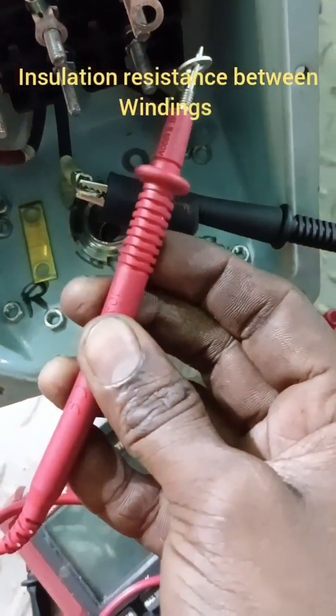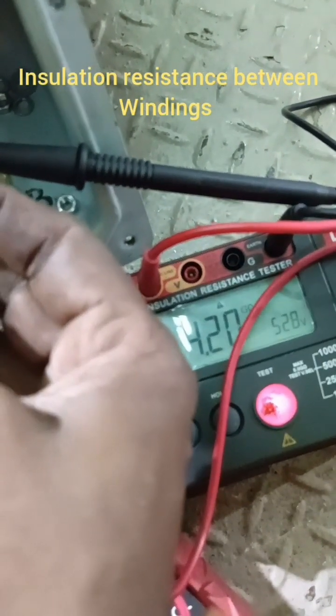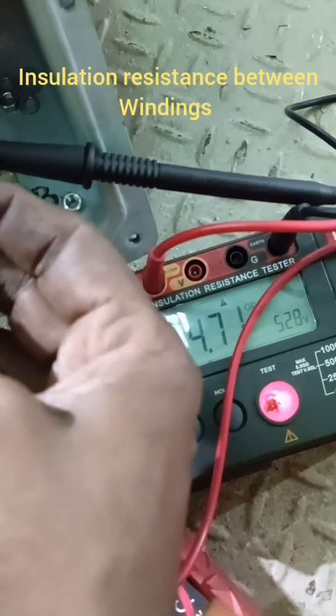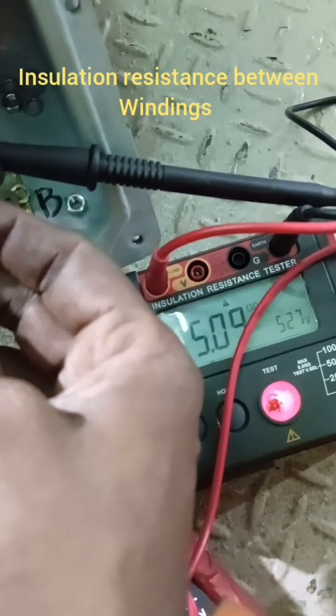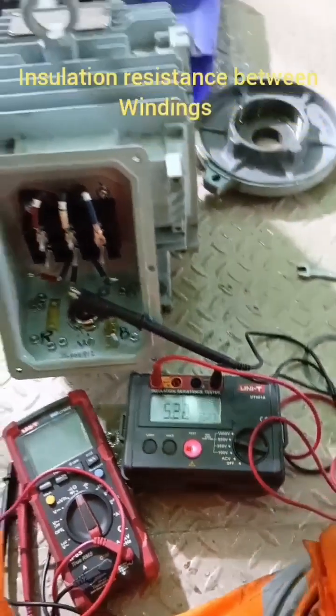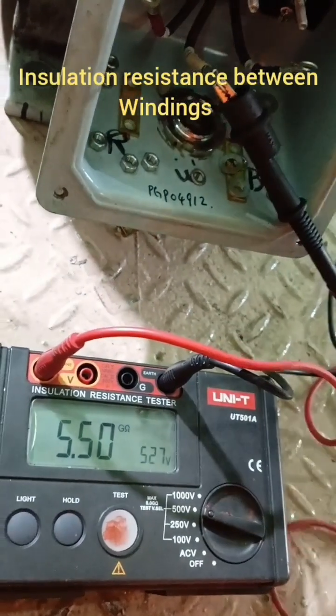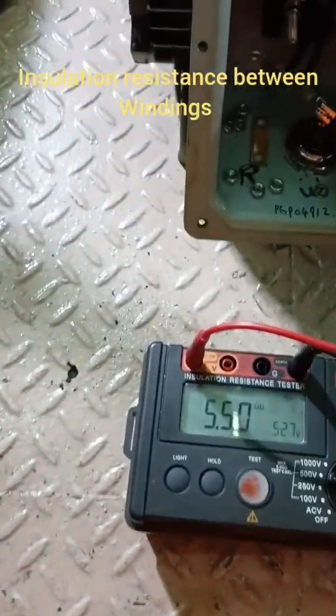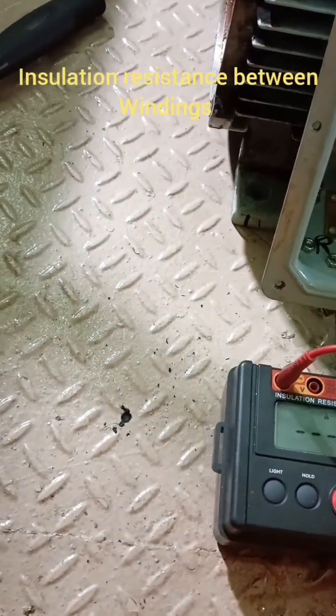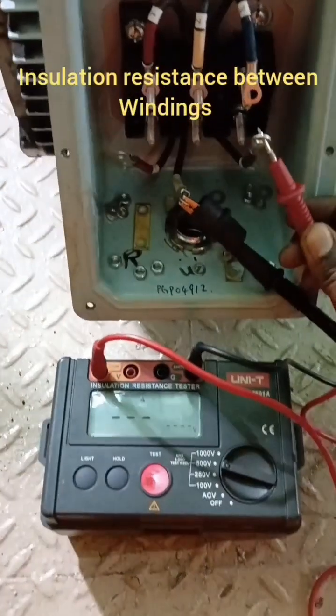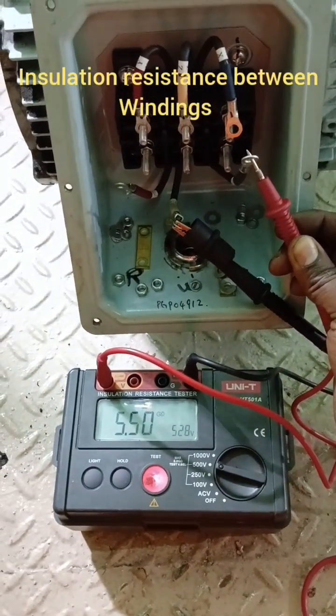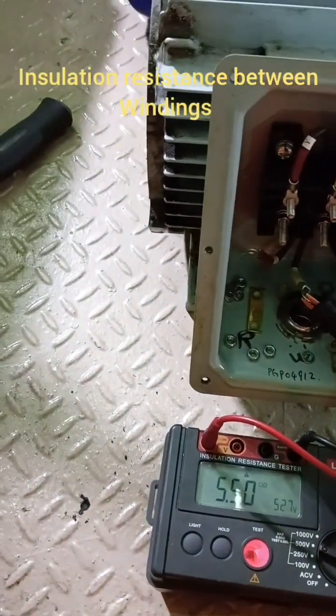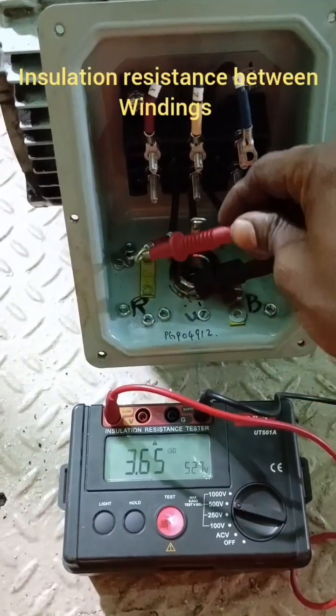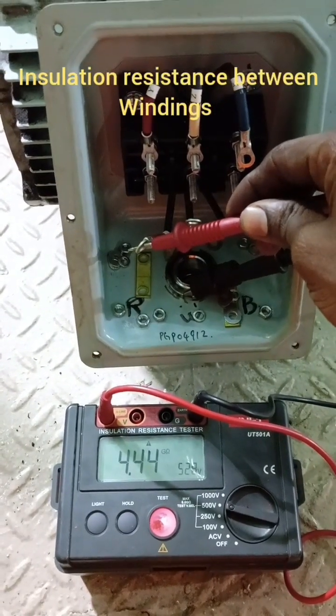This was a good value, so we need not do any additional varnish. When we are doing motor overhauling, if the resistance falls below 1 to 4 megaohms, then apply a little bit of varnish, keep it to dry for a day and assemble the next day. Otherwise, if it is 5.5 megaohms, you can just change the bearings and assemble it back.